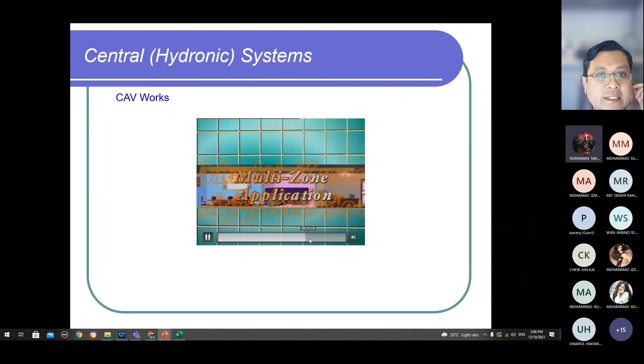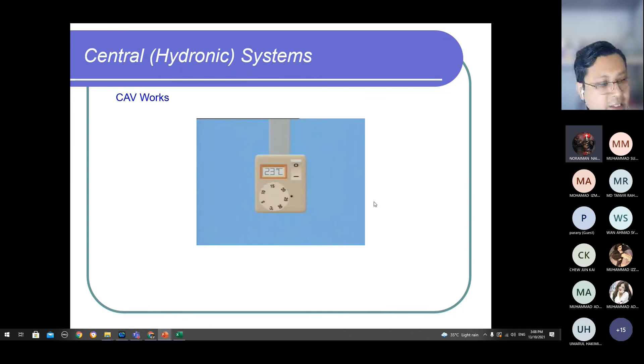Okay, this one is a video. Okay, that will be fast. Let me take it up here. Actually, in the single constant air volume system, we control only one condition for one building. Controlling is central, and then it controls all units. So the sensor, like the video said, is only one, so we cannot represent the other rooms. Some rooms maybe need higher temperature, but we cannot do multiple controlling. So this one is VAV, we can control by multiple conditions.